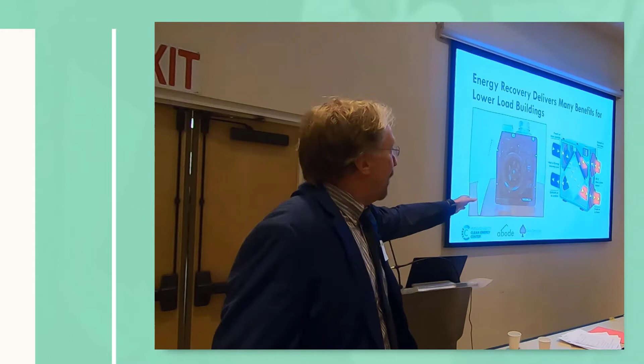Most builders are using the fans. I'm going to be nice about this. Most builders are using exhaust fans only because they're only $200, right? Whereas the HRV is going to be $2,000. So they're looking to save on that and just meet the code. So that's an important thing in terms of heat load. Ventilation, again, mass requirement. You got a choice here, and you want to make sure it's accurate. It's actually the CFM that the ASHRAE standard says it should be for each home.